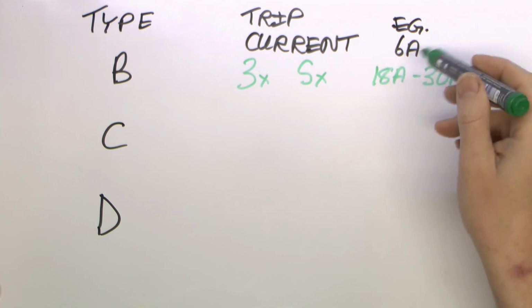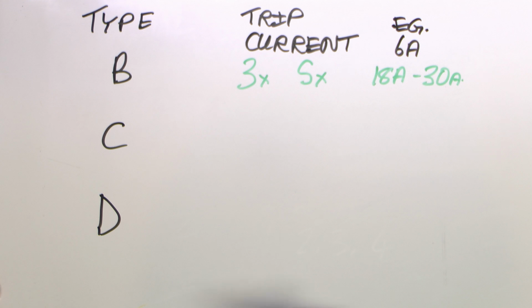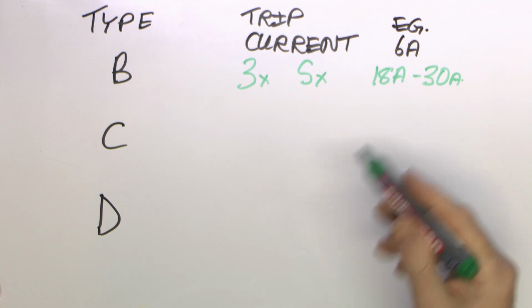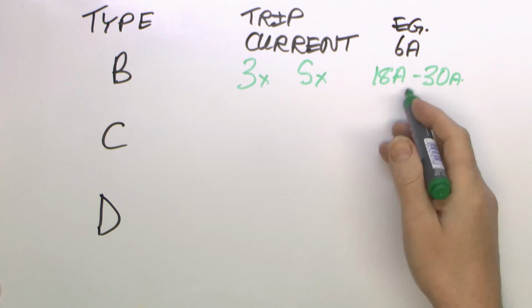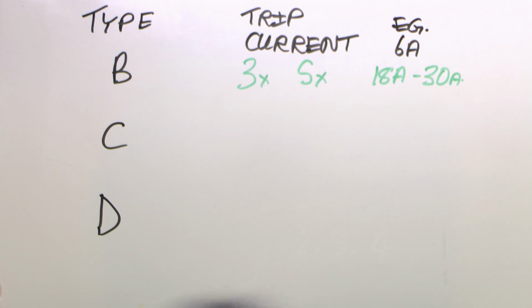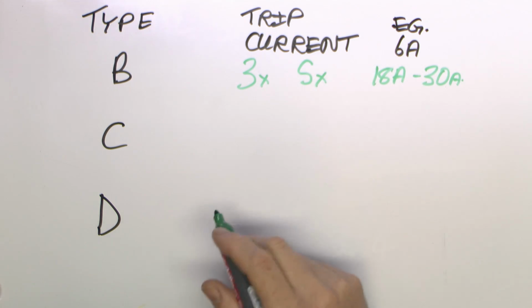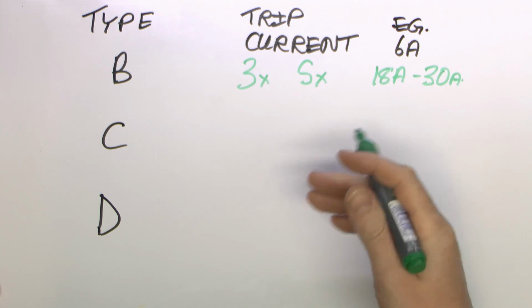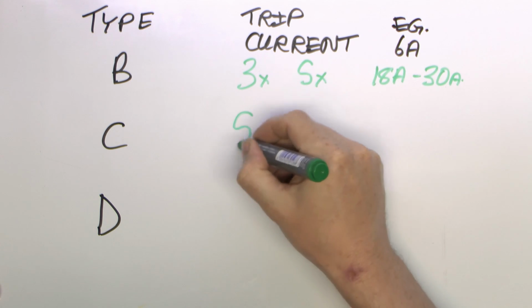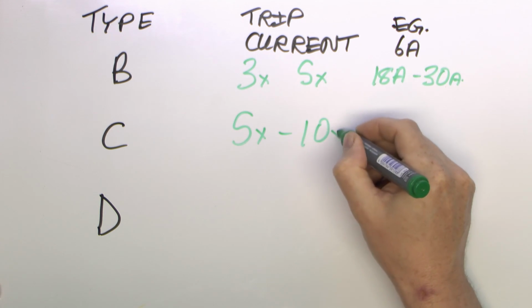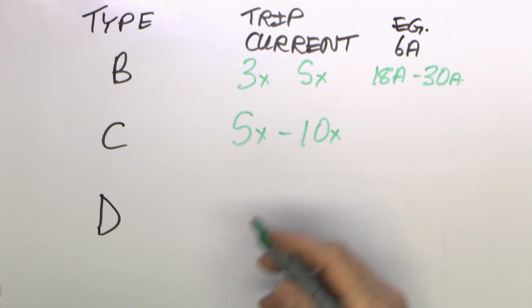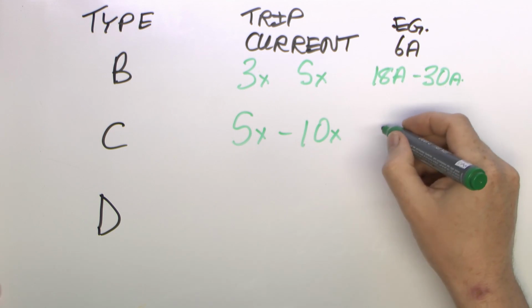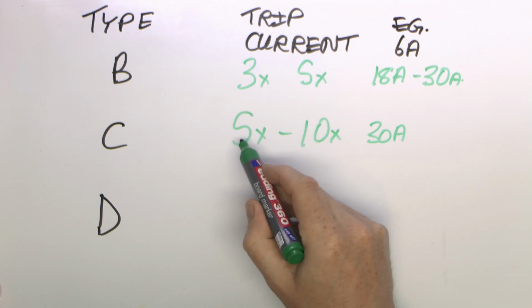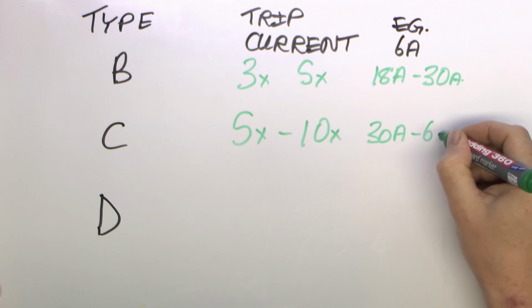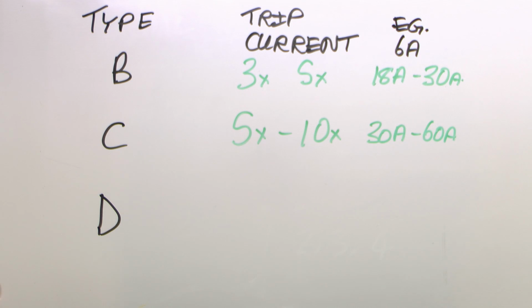So if it did trip at, say, 6.01 amps, all that would happen is every time you turn anything on in your house or wherever, the circuits would just trip out all the time and be useless. So this is actually a design feature. In the case of the Type B, somewhere between 3 and 5 times the rated current. Now the Type C, which is used generally for things which have a larger switch-on surge, will trip somewhere between 5 times and 10 times the rated current. So in the case of a 6 amp circuit breaker, the tripping point would be somewhere between 30 amps, which would be 5 times 6, and 60 amps, which of course is 10 times 6.